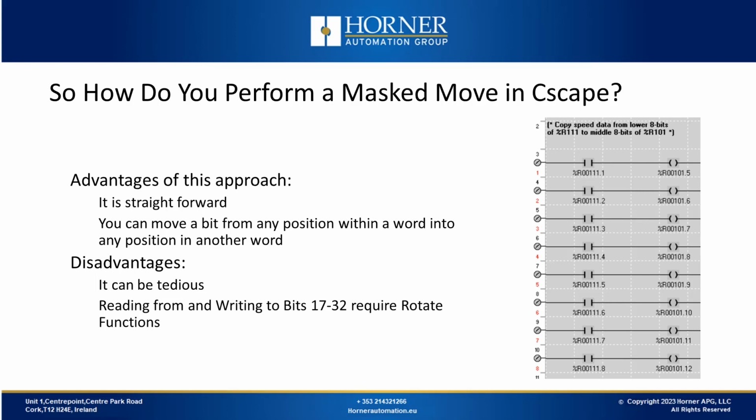Additionally, in variable-based advanced ladder, access to bits 17 to 32 is not available. This limitation affects double word variables when performing a masked move function, at least in Cscape 9.9. However, it's worth noting that Cscape 10 will include this capability.